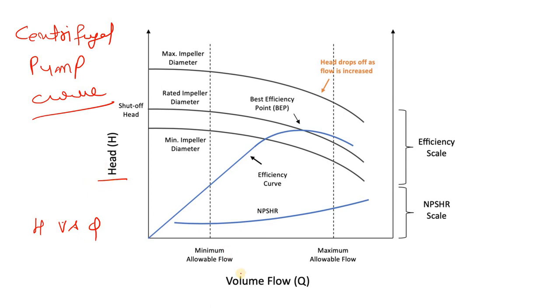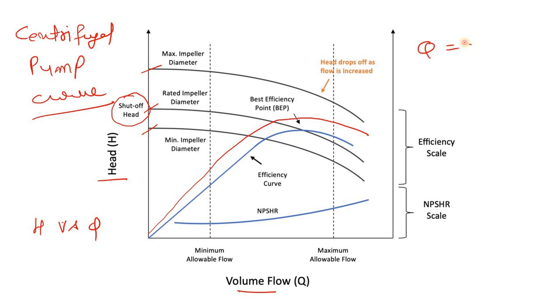The pump curve is head versus Q — the Y-axis is head and the X-axis is flow rate Q. There are three scenarios: maximum impeller diameter, rated impeller diameter, and minimum impeller diameter. To understand shutoff head: whenever the flow rate is zero, the head will be maximum. For the rated impeller diameter, when Q is zero, the head is at its maximum point, and the curve decreases after that.